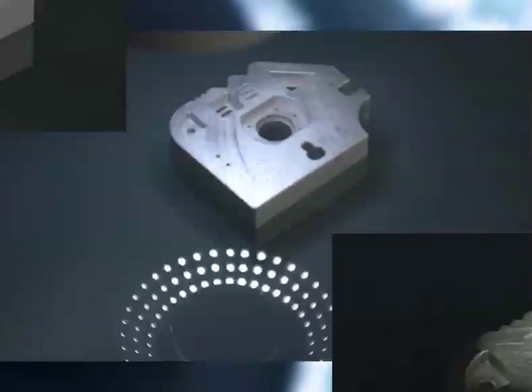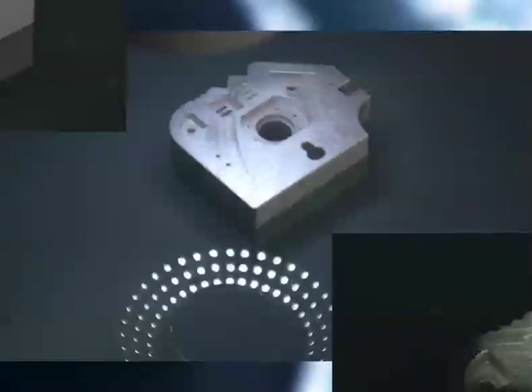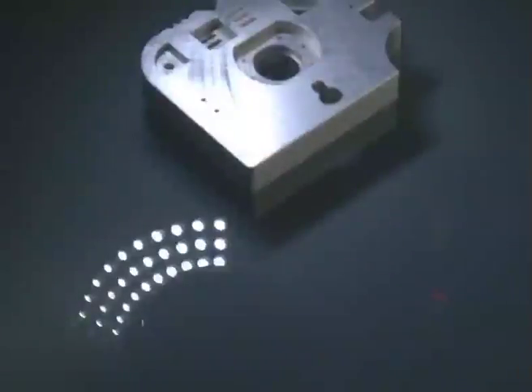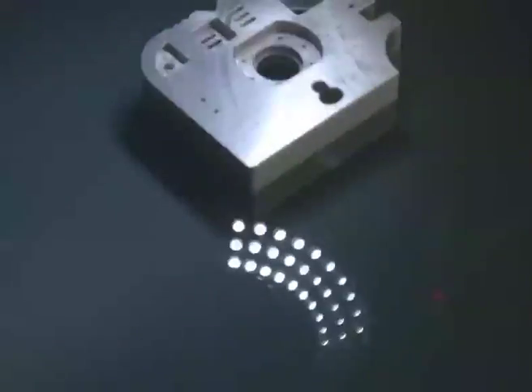The Quick Vision Active series has three high-intensity LED light sources: stage lighting or backlighting that comes from behind the workpiece, coaxial lighting that comes through the lens, and a four quadrant programmable ring light. Note how the appearance of the image changes based on the selected illumination.